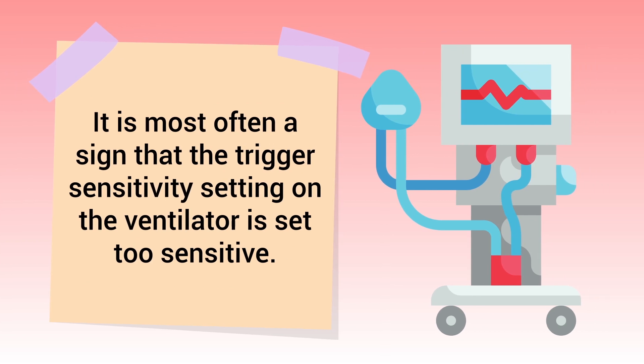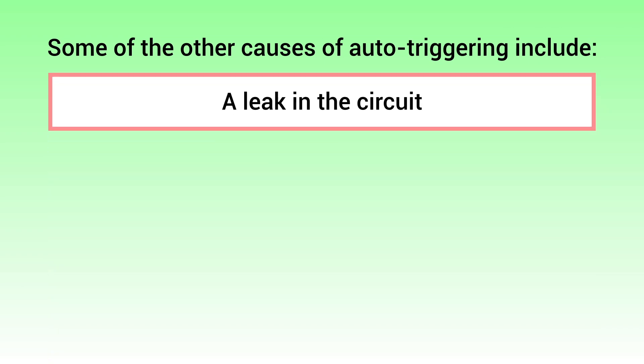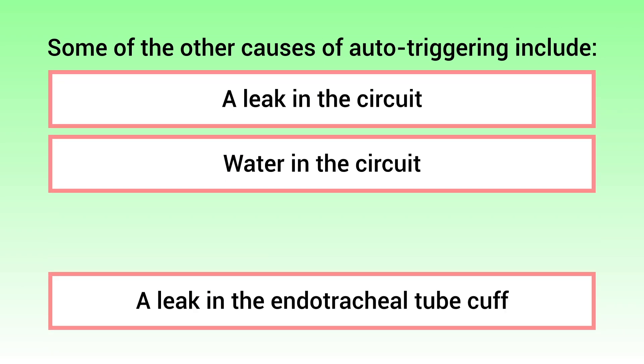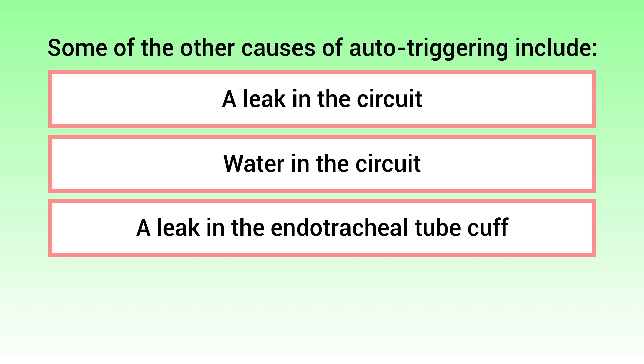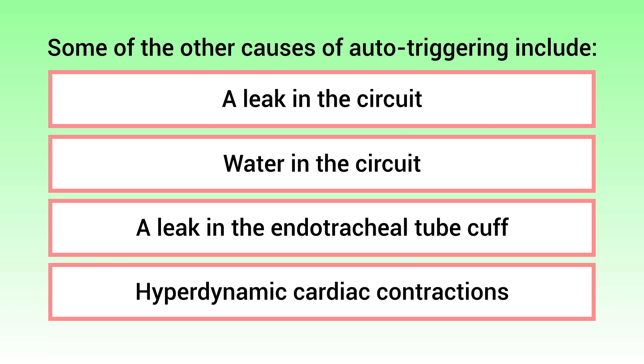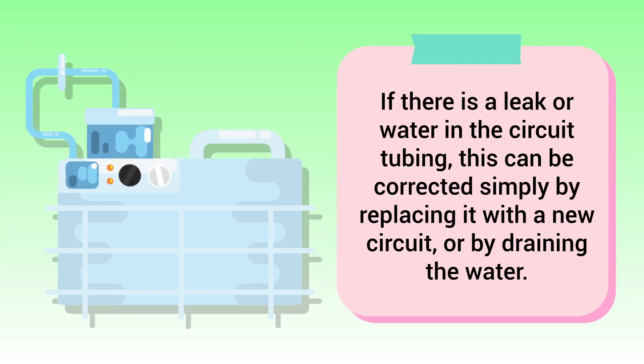When present, auto-triggering is most often a sign that the trigger sensitivity setting on the ventilator is set too sensitive. Some other causes include a leak in the circuit, water in the circuit, a leak in the endotracheal tube cuff, and hyperdynamic cardiac contractions. If there is a leak or water in the circuit tubing, this can be corrected by replacing it with a new circuit or by draining the water.